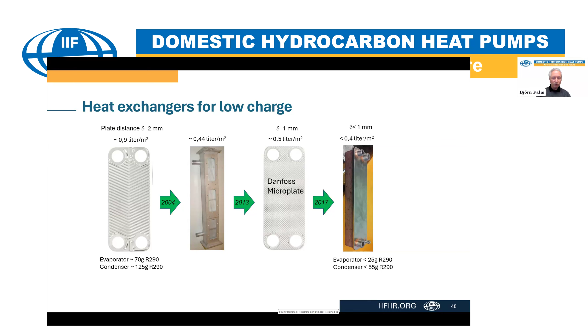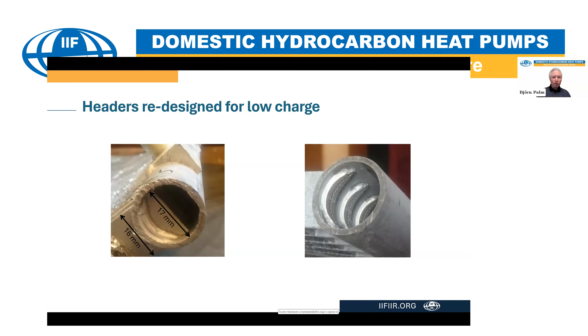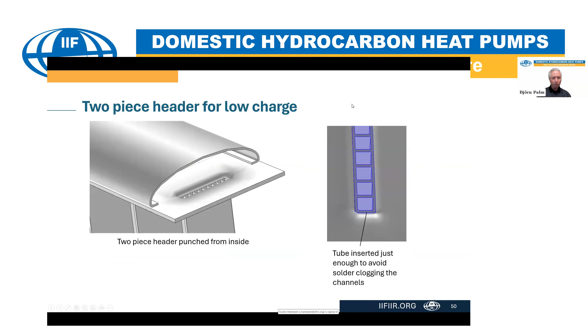If we have an air to water heat pump, we need some air coils. And one of the problems with the air coils is the headers, which usually have quite a large share of the total charge, especially if we use microchannel aluminum tubes for the heat exchanger. But of course, there are ways to decrease the charge here also. And on this slide, you can see another type of header which could potentially be used to reduce the volume of the header and also the amount of charge in the header.